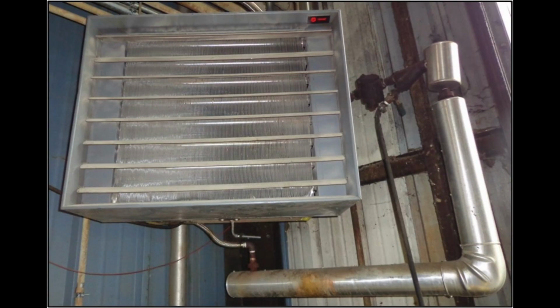That's where, when that heater turns on, that float can instantly respond to the load and then get rid of that condensate and heat your area up very efficiently. Where should a steam trap be installed in relation to the unit heater? Steam trap should be at the lowest point. Often I see steam traps up halfway up the unit heater, as far as on the condensate line side, where you're flooding your heater continuously. So it has to be at the lowest point so we can get good drainage.